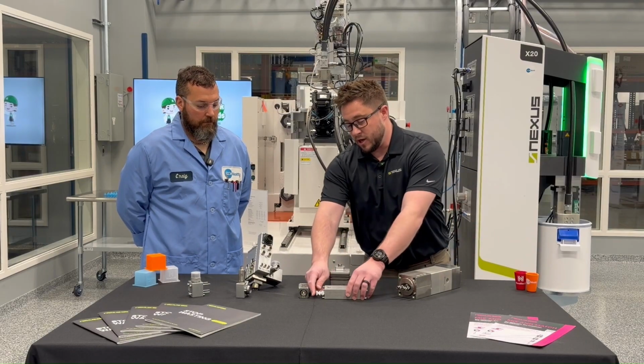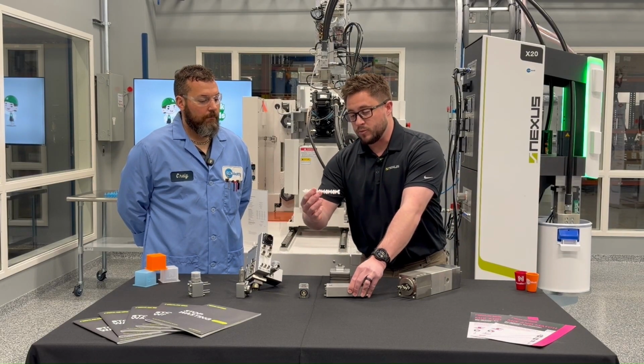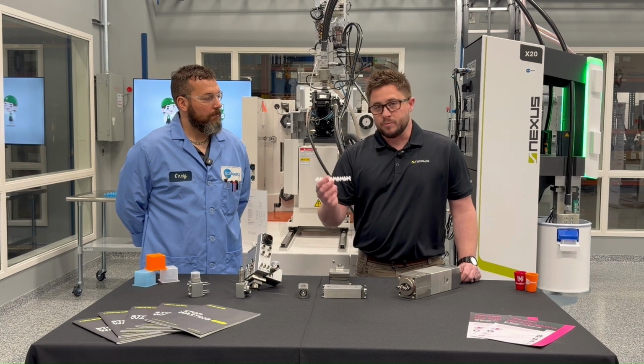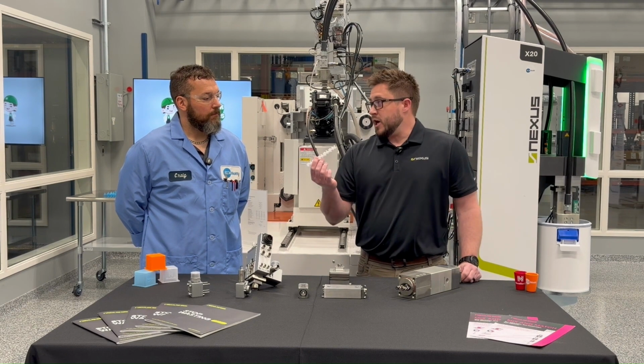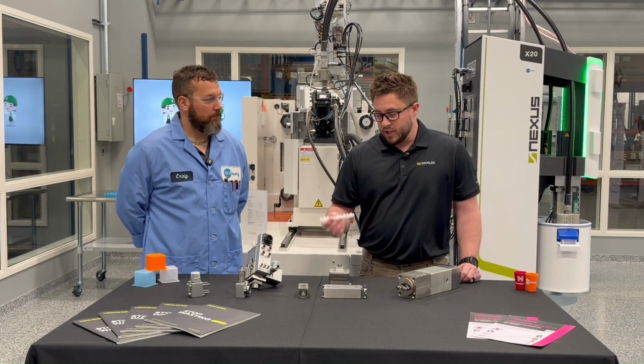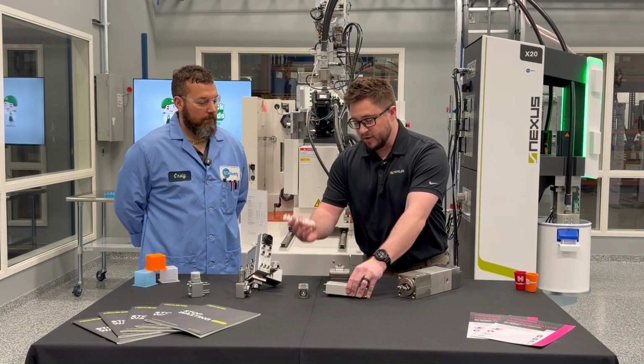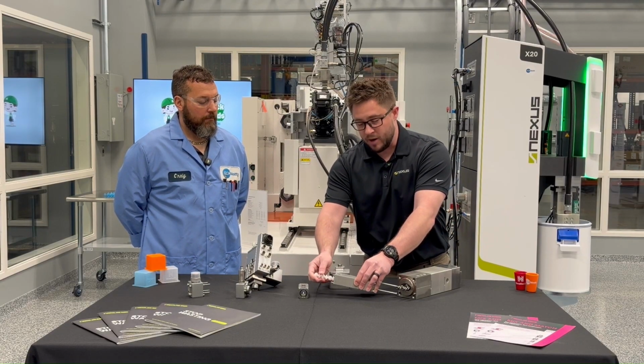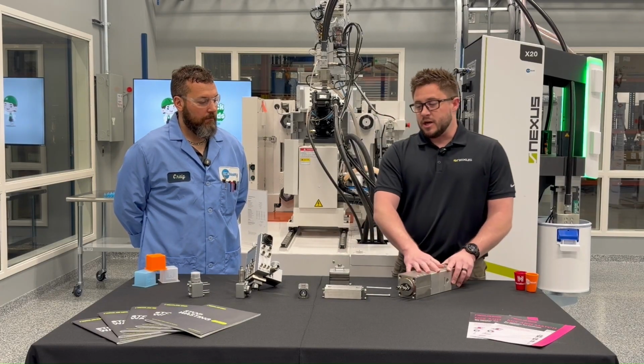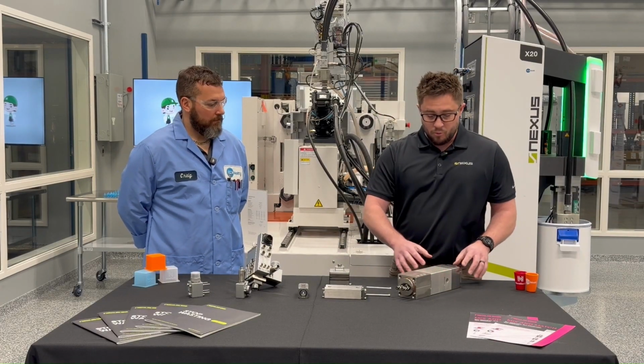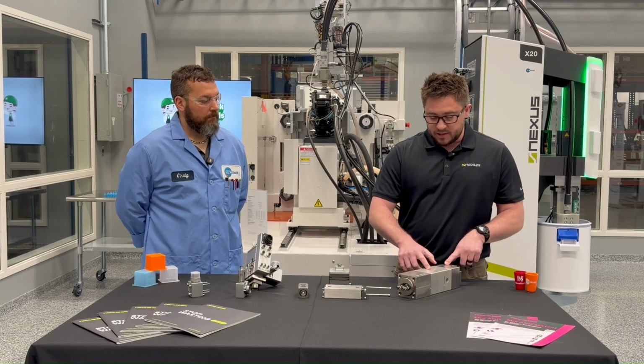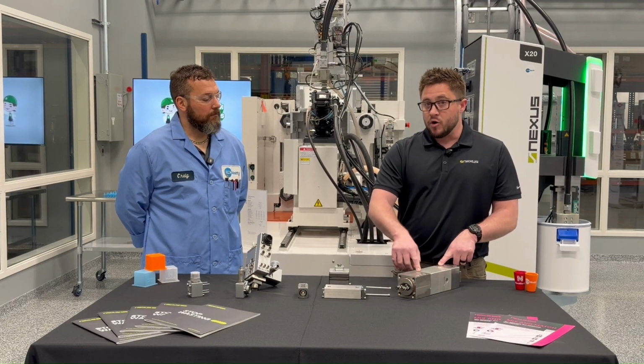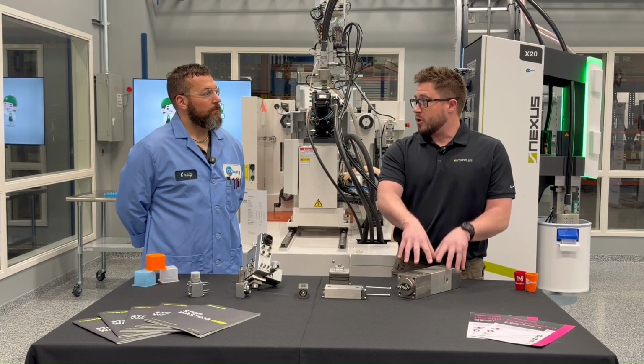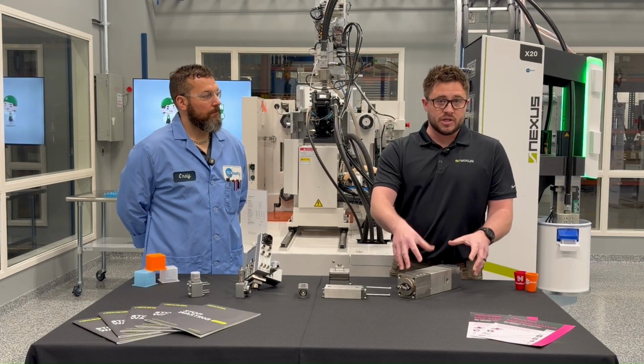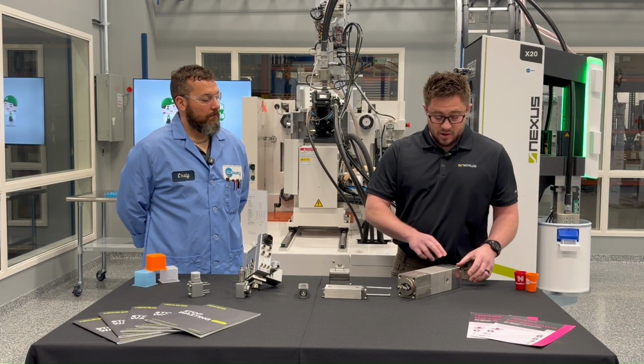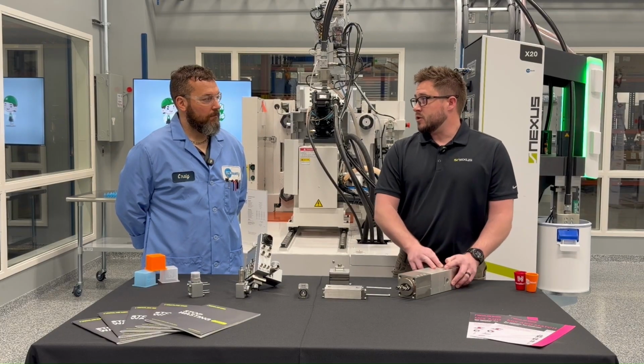For the disposable static mixers, typically we just toss them—trying to clean them takes too much time, so every time we do a cleaning we swap those out. For the pump system itself, same thing, maybe once a year we do a cleaning. In this system we only have O-rings, which is a big advantage over piston pumps. There are only a few O-rings and a few shaft seals, that's all.